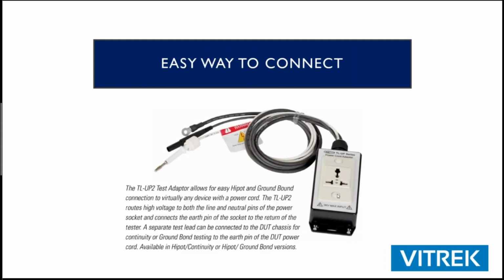So connection. If you are Class 1, this is the way to go right here. What we're doing is breaking out what would be our output terminals into this kind of world power adapter. It works great with the NEMA 5-15 connectors and some other international cords. What this is going to do is apply high voltage to line and neutral. It's going to give you easy connection to your earth ground pin. Nobody wants to be putting alligator clips on these, jumping power cords together, things like that. High voltage is no place to have wire nuts and electrical tape or some heat shrink trying to protect you. I highly recommend buying one of these pre-manufactured boxes. Not only does it reduce your risk, it just makes it so much easier to use.